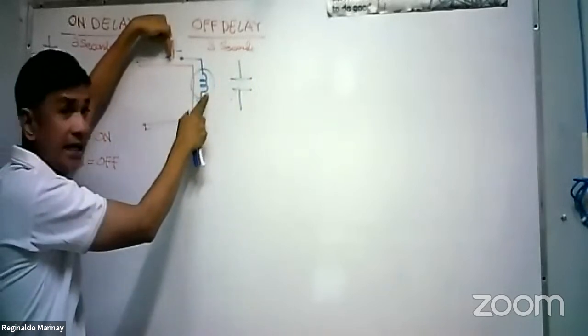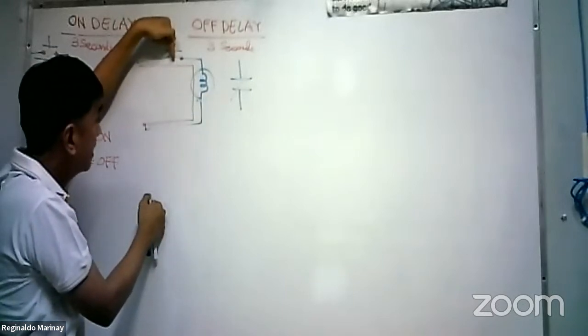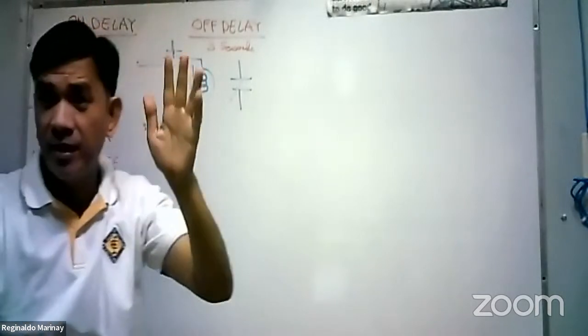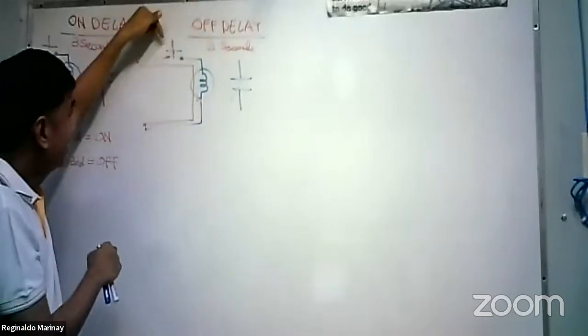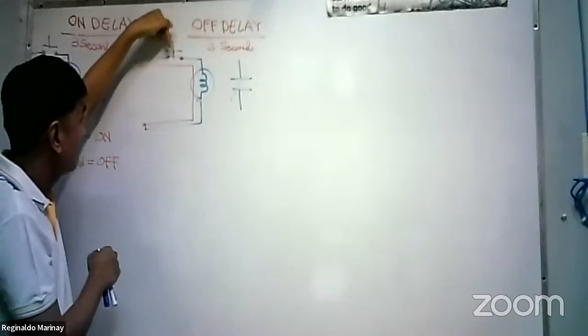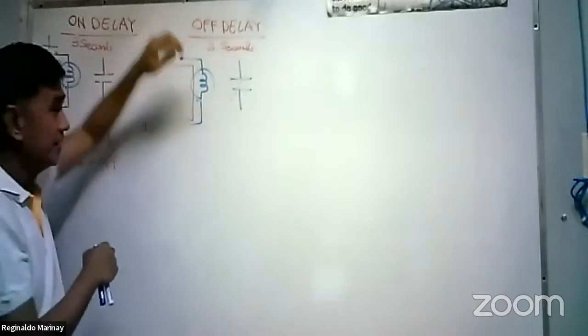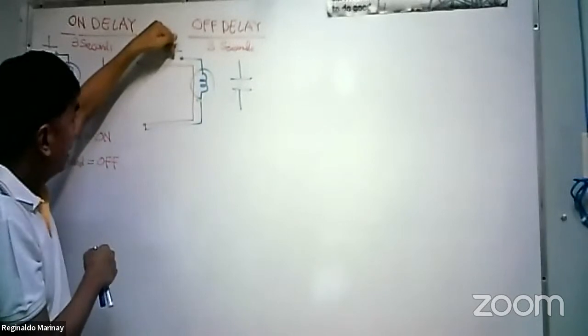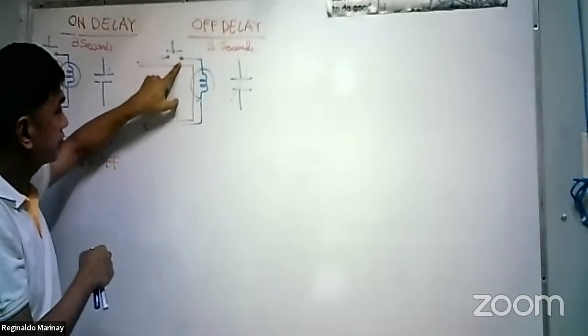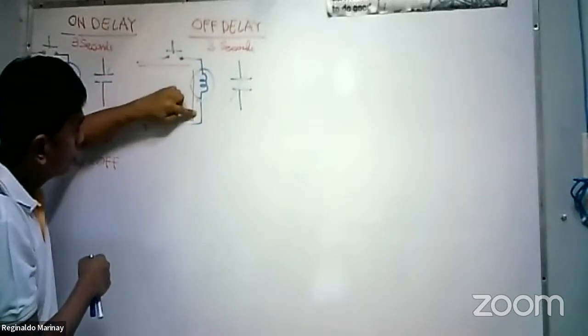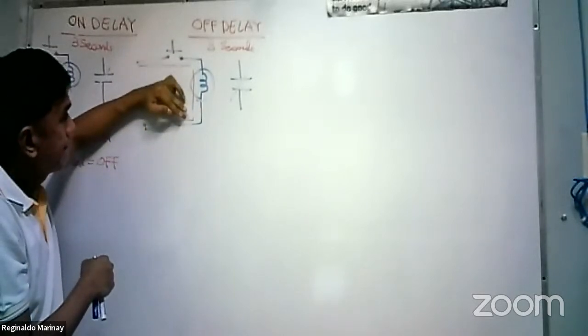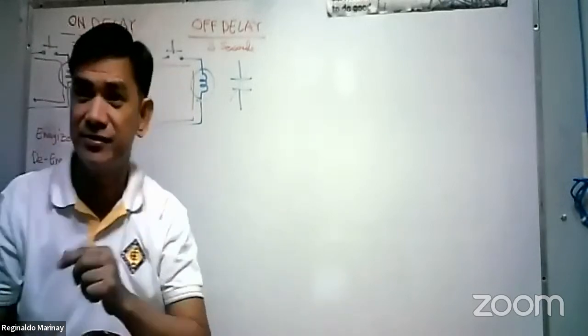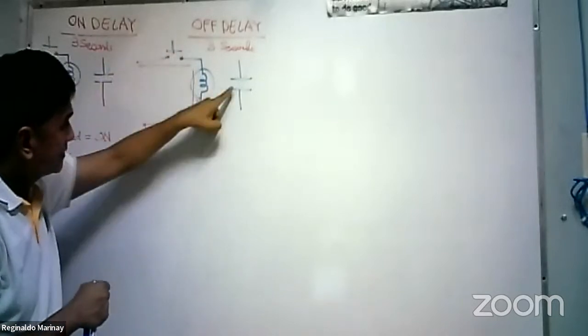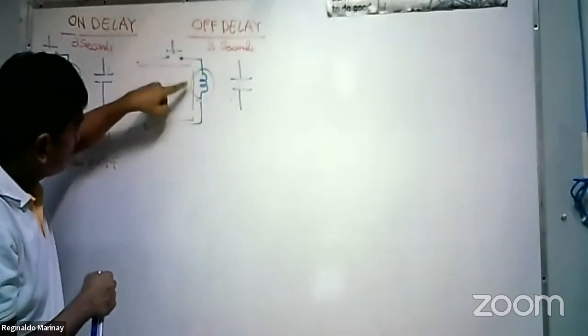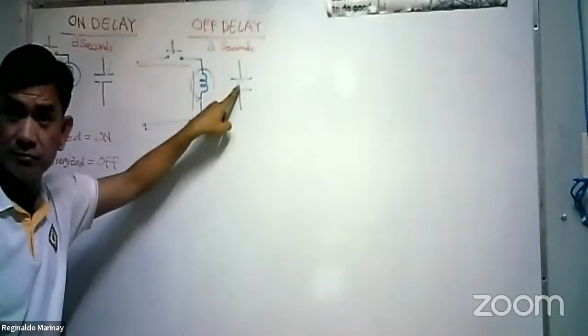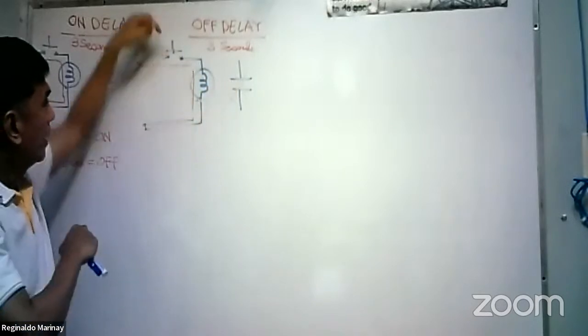Now, if I'm going to de-energize this coil, okay, I will depress this one. Depress. Press, depress. Okay? But do not be depressed. Okay? Okay. So please listen carefully. Do not be depressed. Okay. I will press this. I just mean depress is when you release your finger. That is already the depressed position. Right? So, if I am going to depress this one, that will become open. The circuit becomes open. Okay? De-energizing your holding coil. This becomes de-energized. As this becomes de-energized, it will start counting 3 seconds. Remember, once this becomes de-energized, before it de-energizes, that is closed. Once this becomes de-energized, this is still closed until you reach 3 seconds. Okay. Once, again.